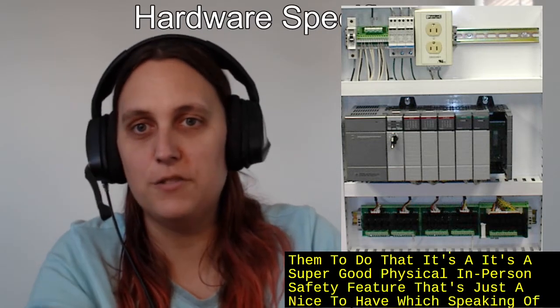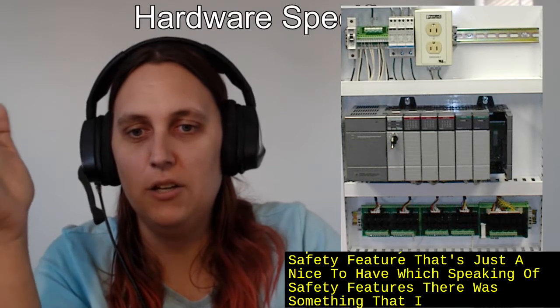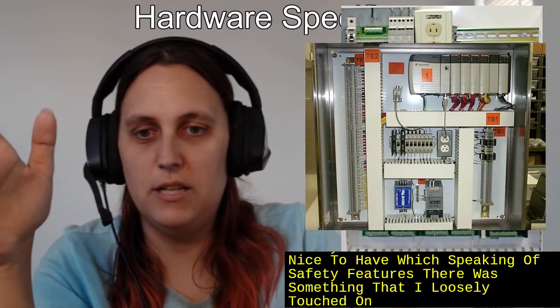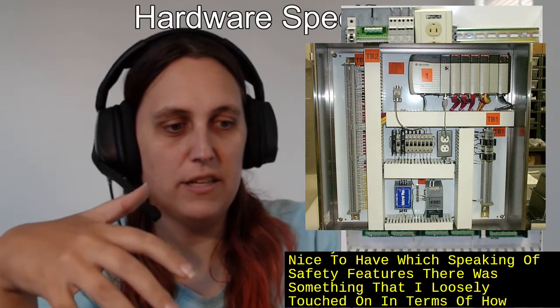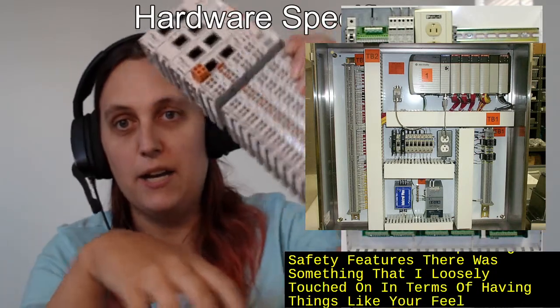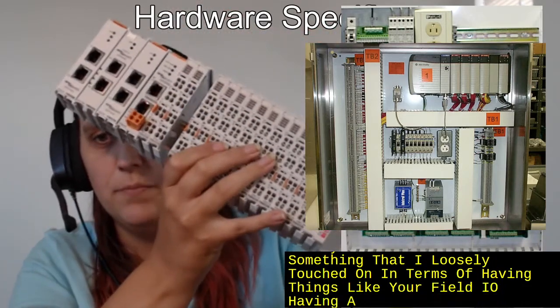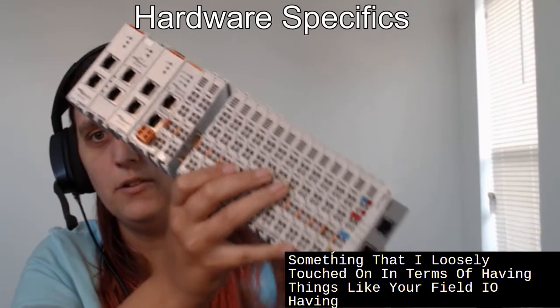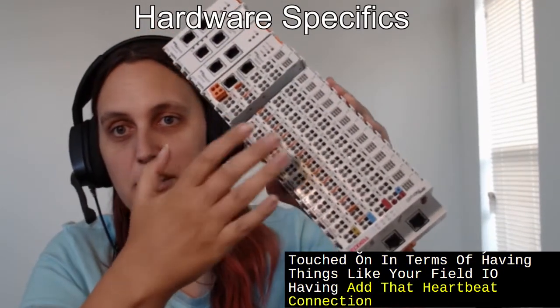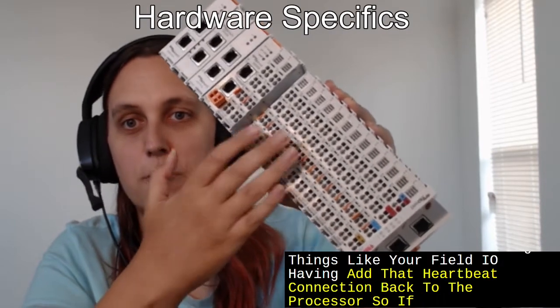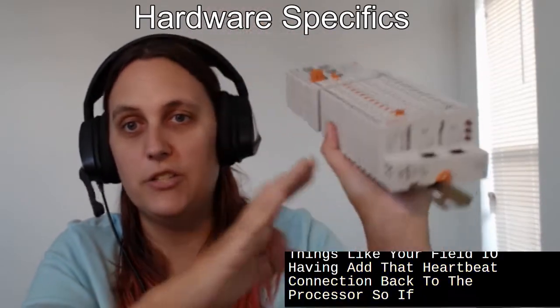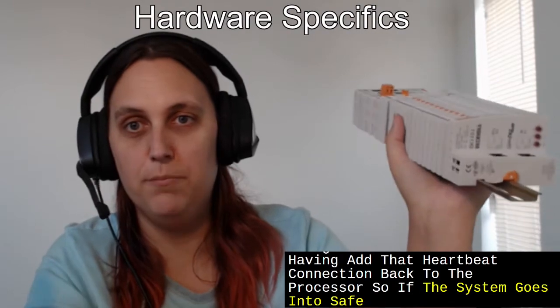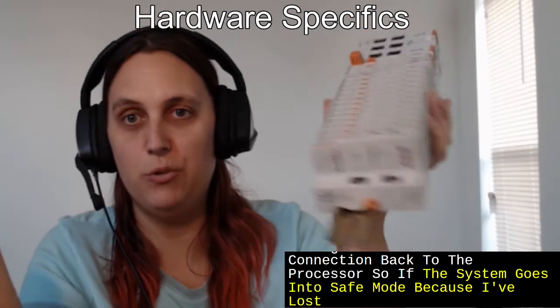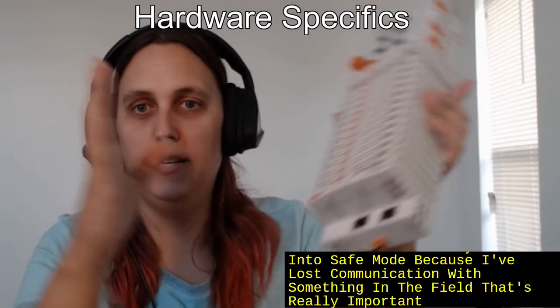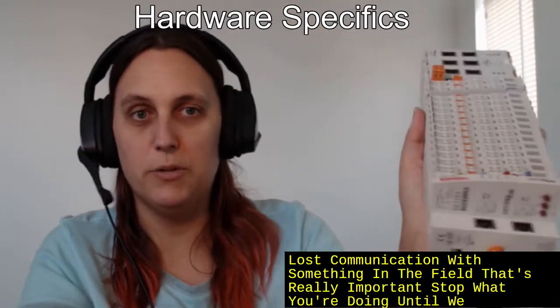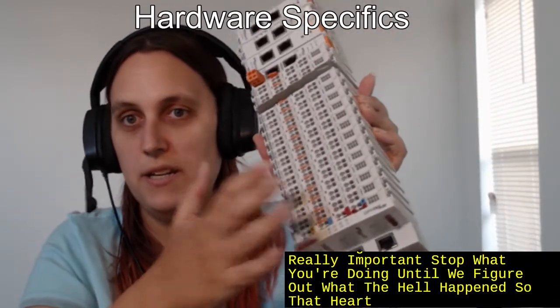Speaking of safety features, it was something that I loosely touched on in terms of having things like your field I/O having that heartbeat connection back to the processor. So if that heartbeat ever stops, the system goes into safe mode because I've lost communication with something in the field that's really important. Stop what you're doing until we figure out what the hell happened. So the heartbeat is a safety feature.